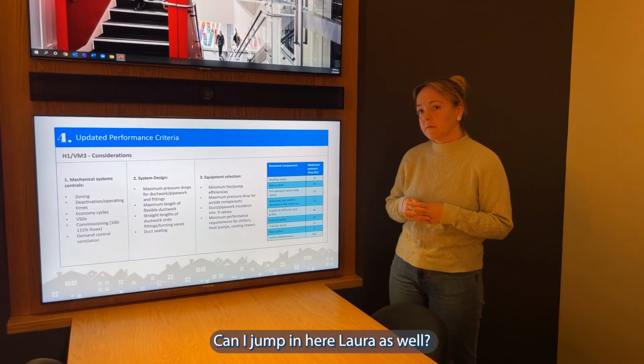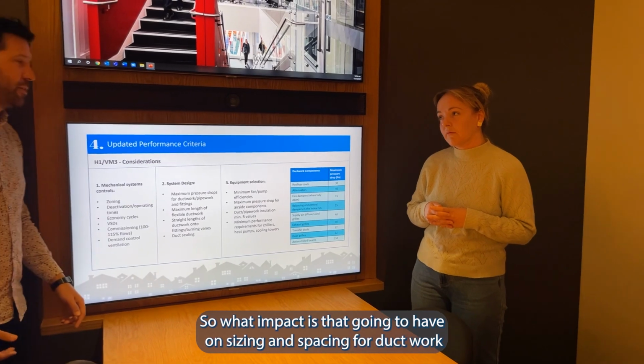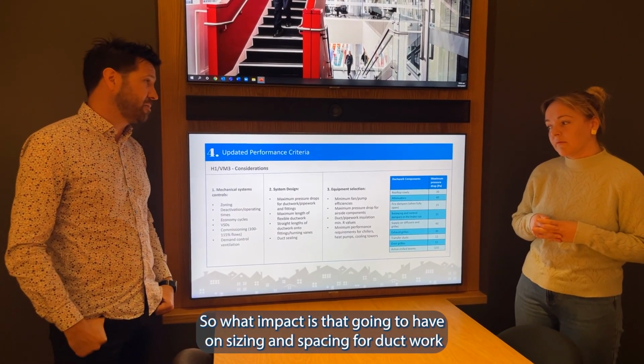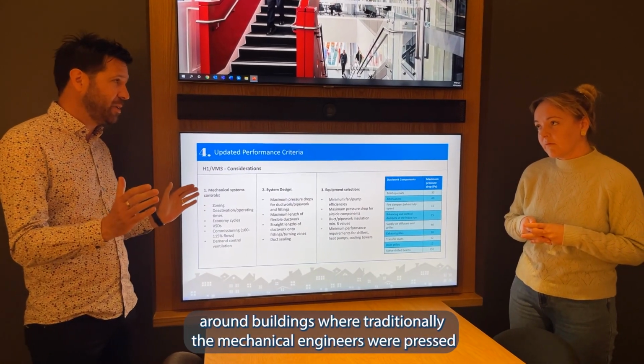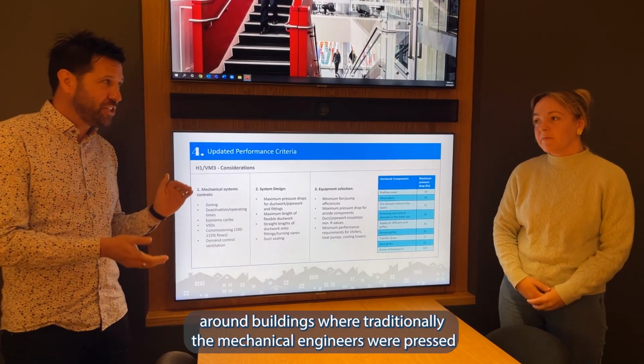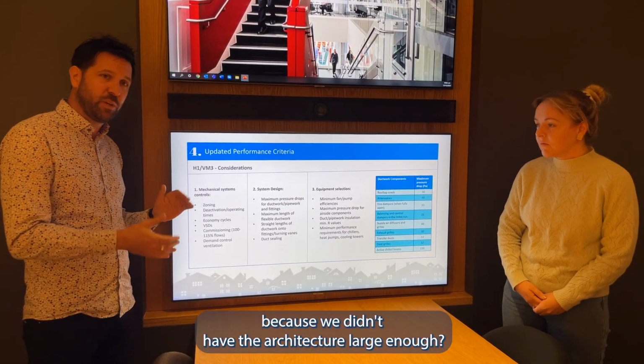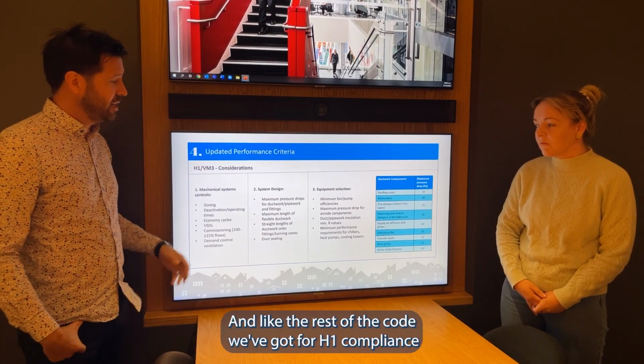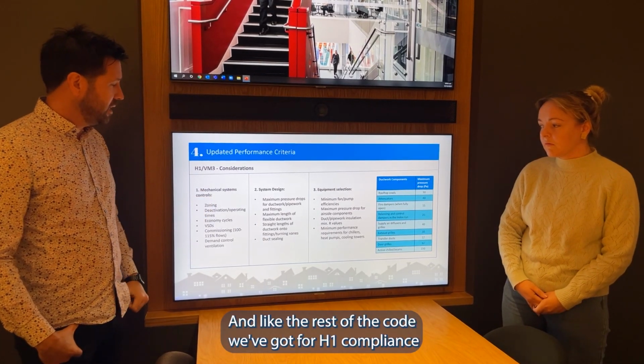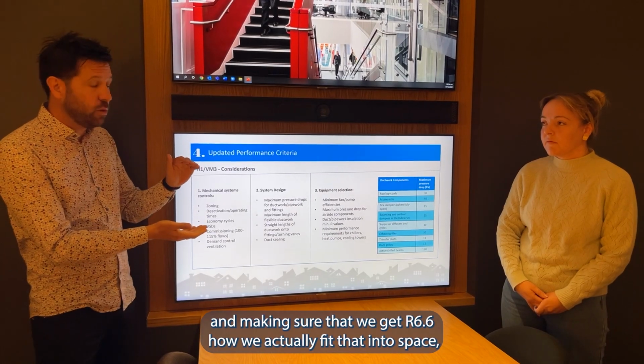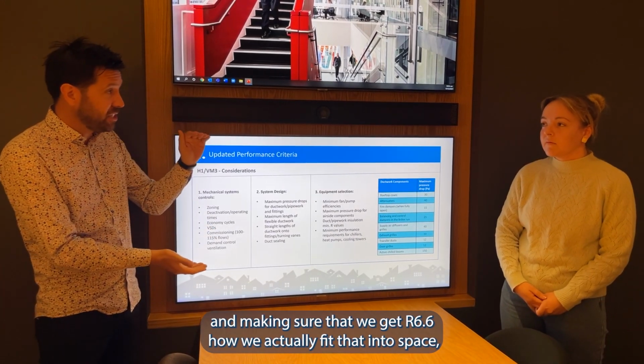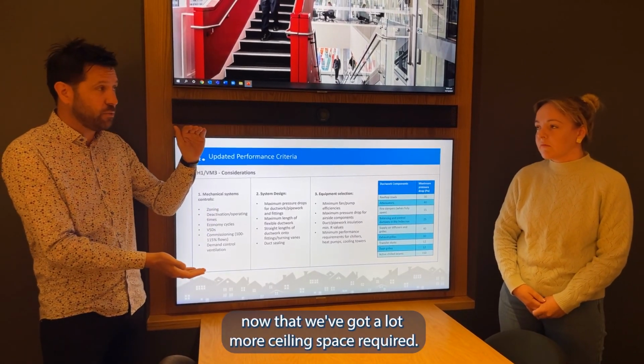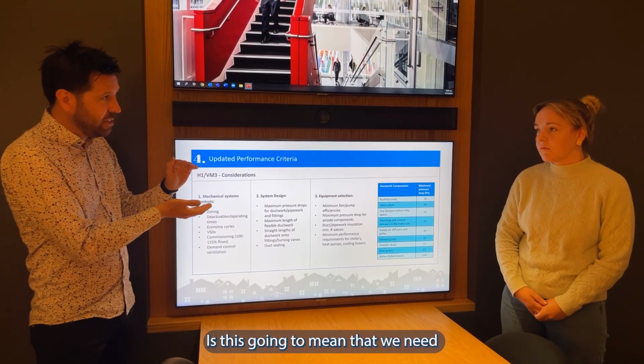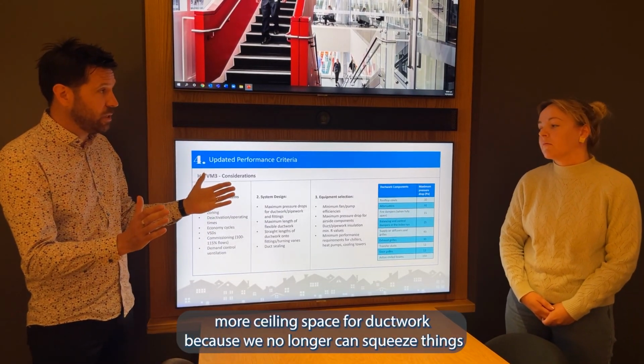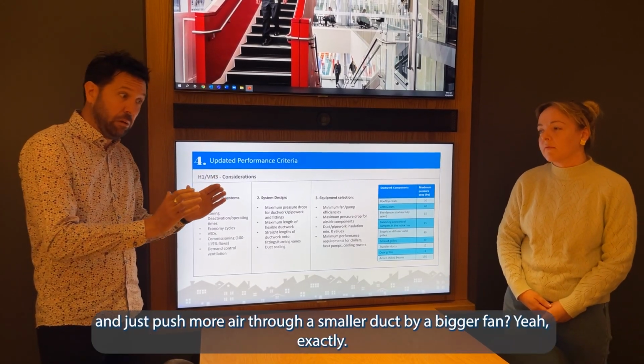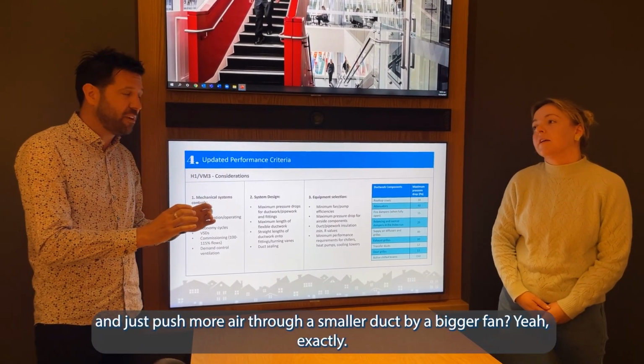Can I jump in here, Laura, as well? So what impact is that going to have on sizing and spacing for ductwork around buildings, whereas traditionally the mechanical engineers were pressed and squished on some of the duct requirements because we didn't have the architecture large enough, and like the rest of the code that we've got for H1 compliance and making sure that we get R6.6, how do we actually fit that into space? Now we've got a lot more ceiling space required. Is this going to mean that we need more ceiling space for ductwork because we no longer can squeeze things and just push more air through a smaller duct by a bigger fan? Yeah, exactly.